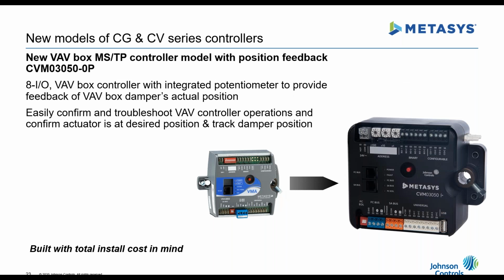We're also introducing an 8-point VAV box MSTP controller with an integral potentiometer to sense actual damper position, the CVM 03050-0P. The actual damper position is represented as a data point that can be seen in the Metasys UI, and there are built-in diagnostics that identify when a mismatch of commanded versus actual position occurs. This allows you to easily confirm and troubleshoot VAV controller operations, confirm that the actuator is at the desired position, and track the damper position.